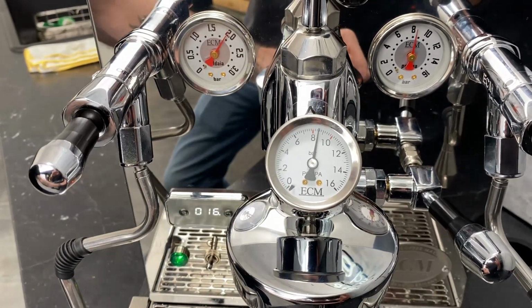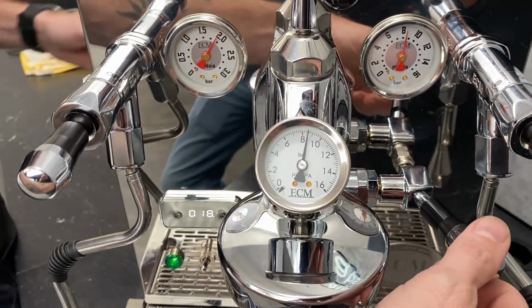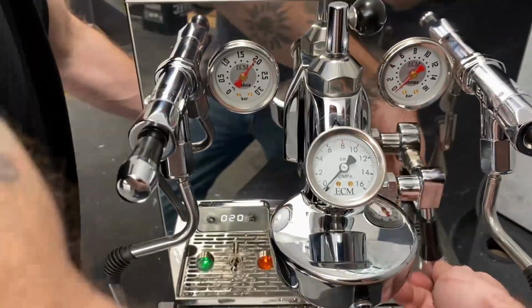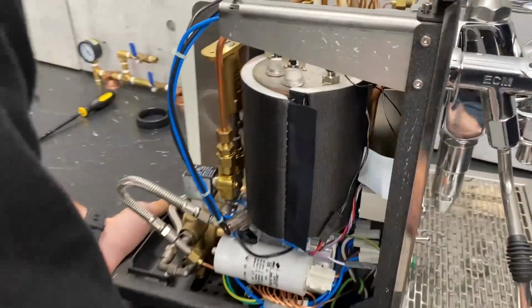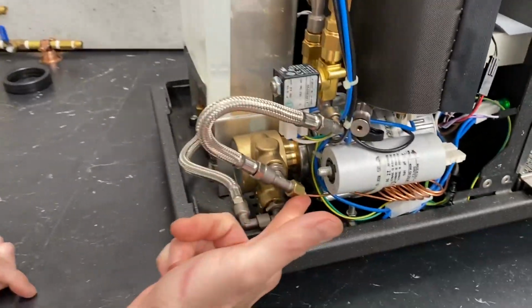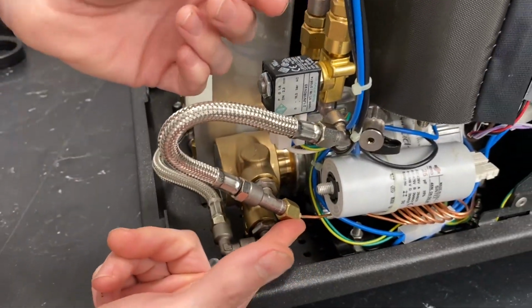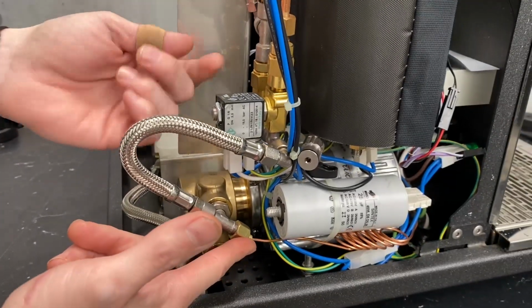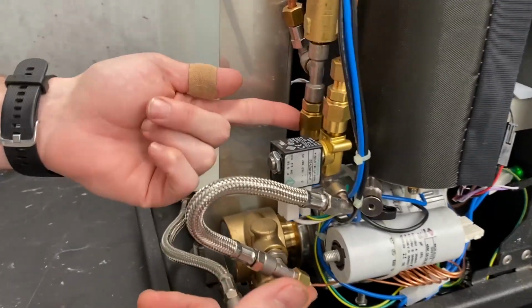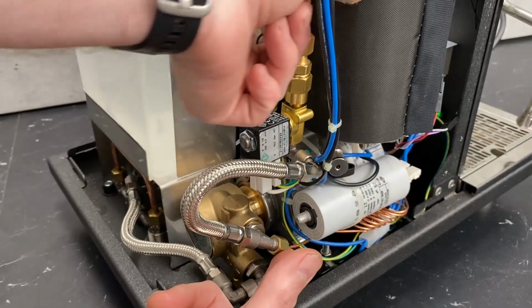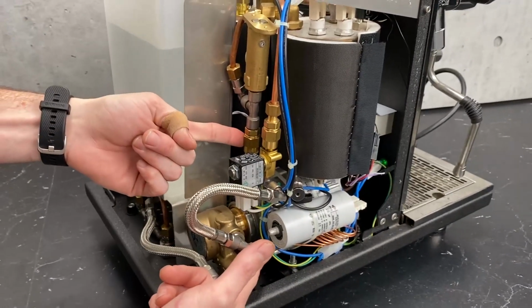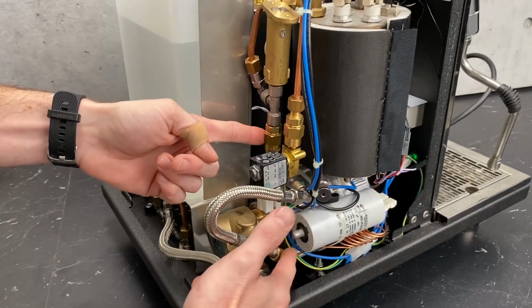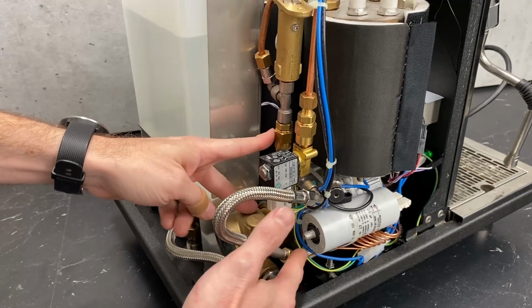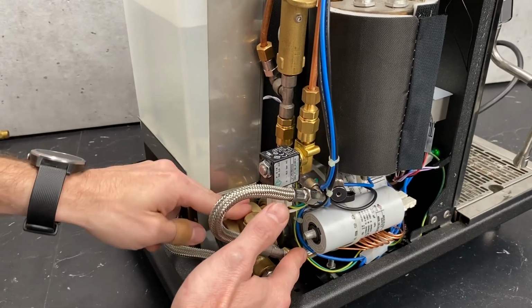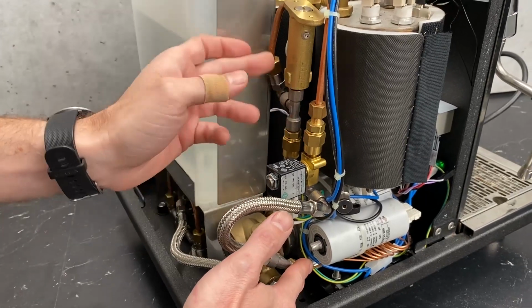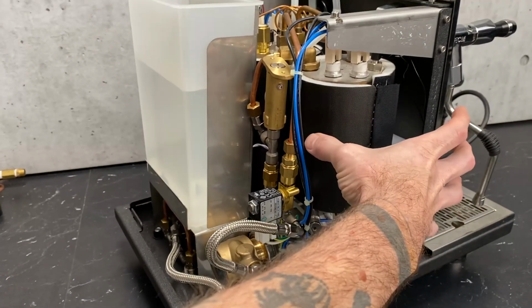The reason behind that is because if you look at the back of the system here, your gauge is right here - that's where the pressure reading is being taken. And there's a non-return valve right here before it goes into your boiler. So the pressure you're going to see on the gauge is just what's coming out of the pump, not what has made it past here into the rest of the system.